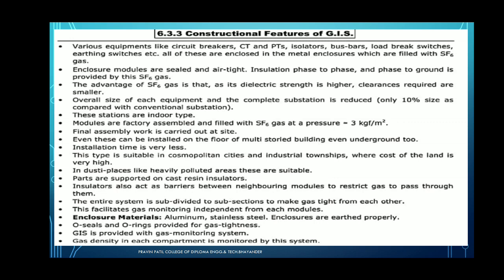Enclosure modules are sealed and airtight. Insulation phase to phase and phase to ground is provided by SF6 gas. The advantage of SF6 gas is that as the dielectric strength is high, clearance required is smaller, and the overall size of each equipment and the complete substation is reduced, only 10% size as compared with the conventional substation. Means size of the equipment is reduced, substation is low size, and hence it requires less space as compared to the conventional substation.